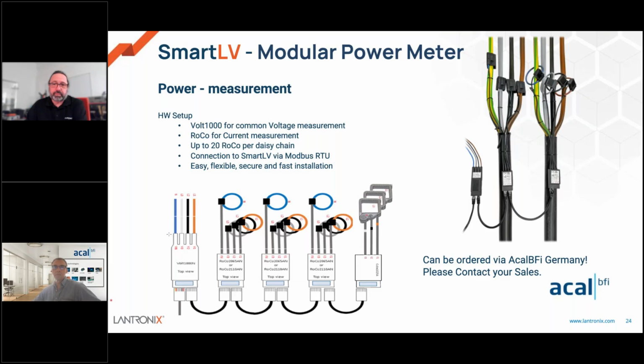The modular power meter consists of a voltage meter, the Volt 1000, and current meters with a Modbus interface. You can see the voltmeter, the Volt 1000, on the left, and the current meters connected to it on the right. The voltage module, the Volt 1000, measures L1, L2, L3, and N, and up to 20 current modules measure power and current. In other words, for up to 20 three-phase plus N outgoing power lines, it's possible to measure the voltage, current, and power for three phases, plus the voltage and current in the neutral.